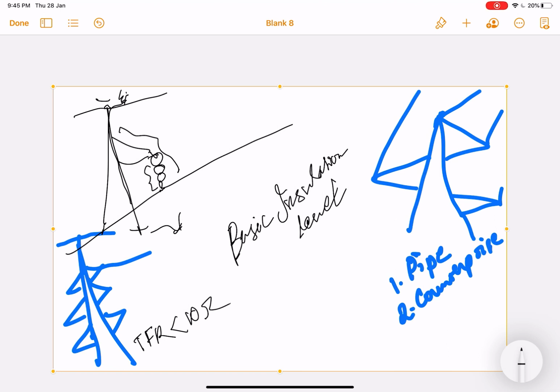Some insulators are designed to handle these lightning impulses. For some 765 kV towers, we have 1550 kV. Similarly, for 400 kV towers, we have 1050 kV. It may also differ according to the design of the insulator. So it may so happen that the voltage currently across the tower exceeds the basic insulation level of the insulator.